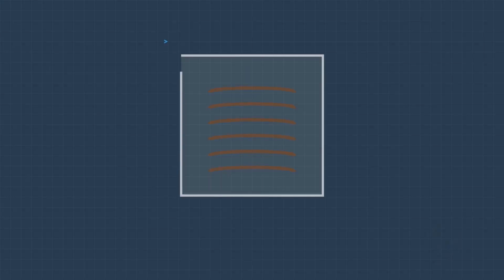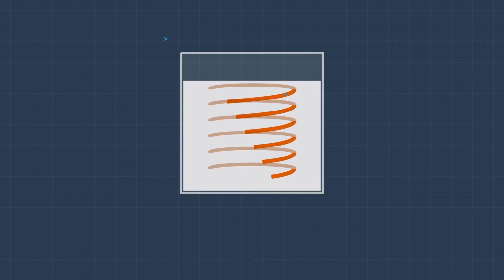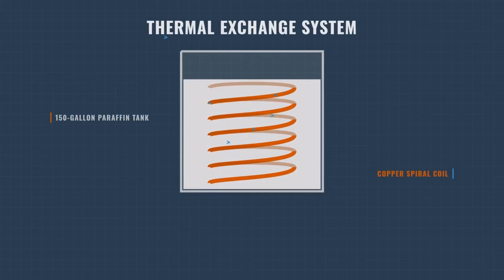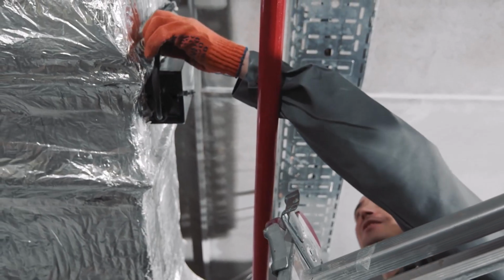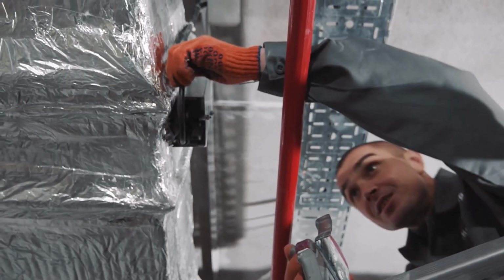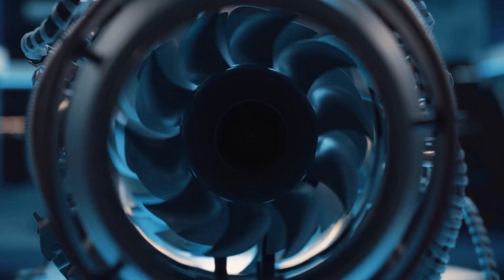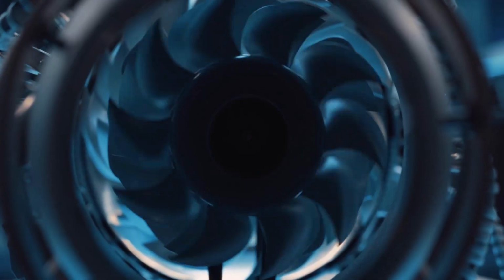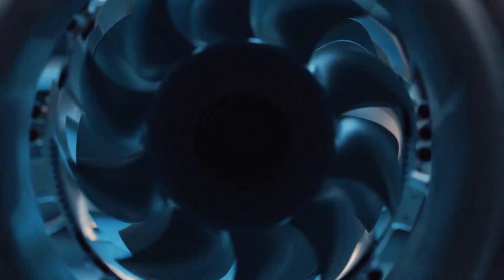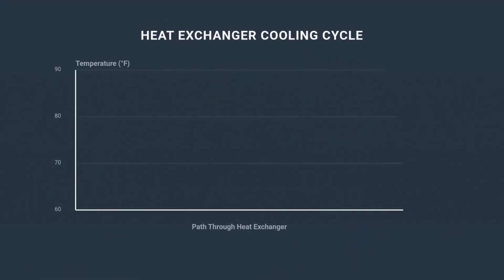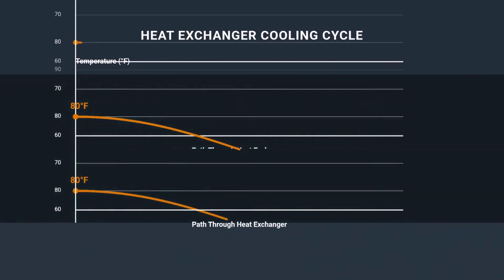This copper coil is the heat exchanger between the home's circulating air and the paraffin mass. Connect the coil to an air distribution loop using 6-inch insulated ductwork. Install a 200 CFM inline fan on the return side of the loop. During peak daytime hours, the fan circulates room air through the coil submerged in the paraffin. The paraffin absorbs heat from the circulating air, holding coil outlet temperature at 64 to 68 degrees until the last gram of wax completes its phase transition.